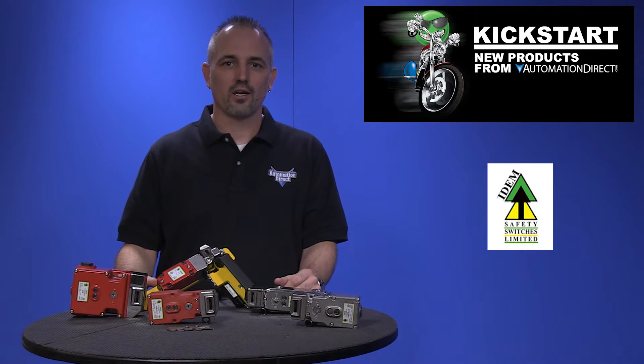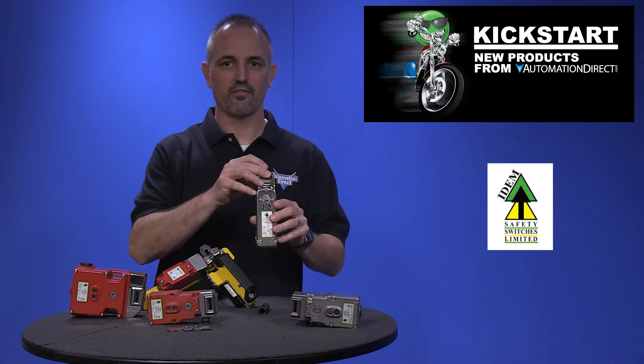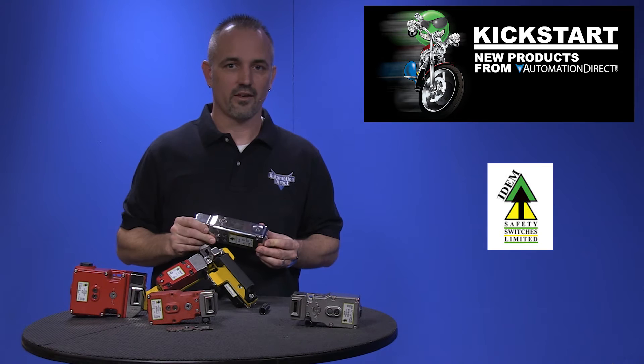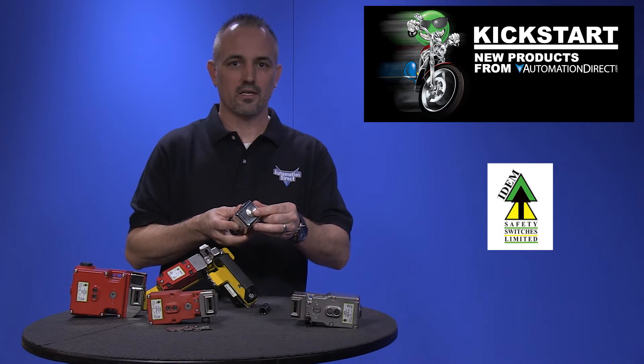These IDEM solenoid locking switches offer auxiliary contacts and LEDs for diagnostic feedback. They have a manual solenoid override for emergency access, and wiring to the units is through a half-inch NPT conduit opening.